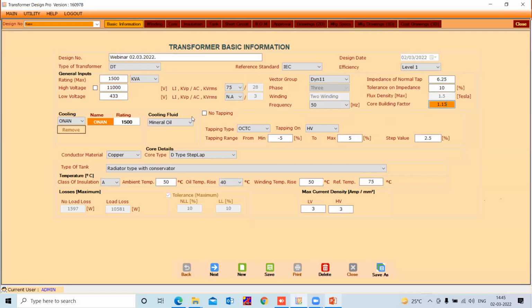You can go for the cooling. Cooling has various options. You can go for ONN, ONAF, OFAF, ANAN, that is dry type in VPI, as well as for cast resin. You can go for the ester oil. The moment you go for the ester oil, you can see natural ester, synthetic ester, both the options are possible over there. Now for this 1500 kVA design, whichever cooling you wish to set, please set it, and let's go further. You have chosen it to be ONAN with mineral oil.